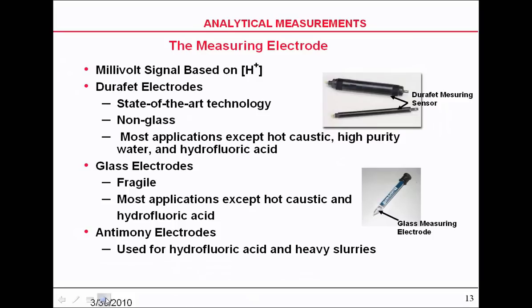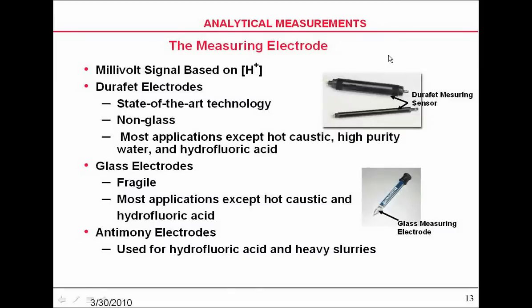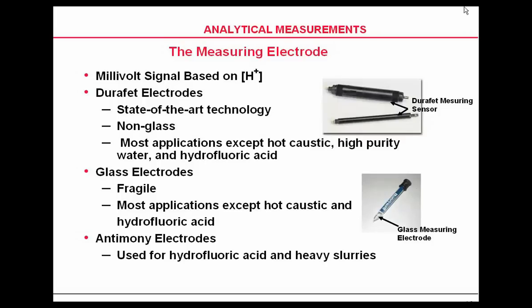We've mentioned up to this point glass electrodes. It's also important to note that Honeywell has available a non-glass pH probe. Honeywell calls them DuraFETs. It's a FET technology at the end, a field-effect transistor, and it's a state-of-the-art technology, non-glass. It's used in applications, almost every application except hot caustic, high-purity water.